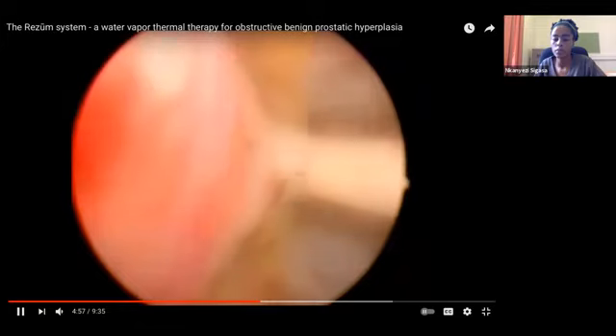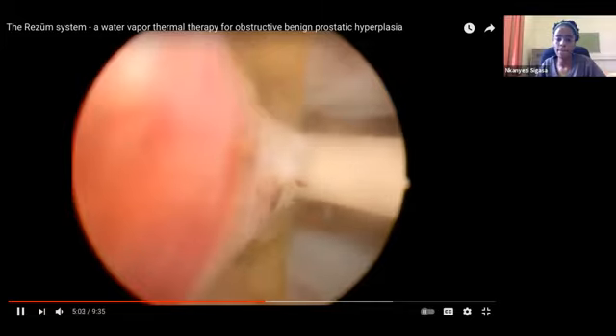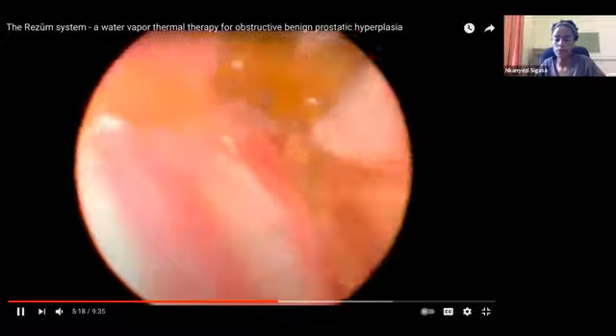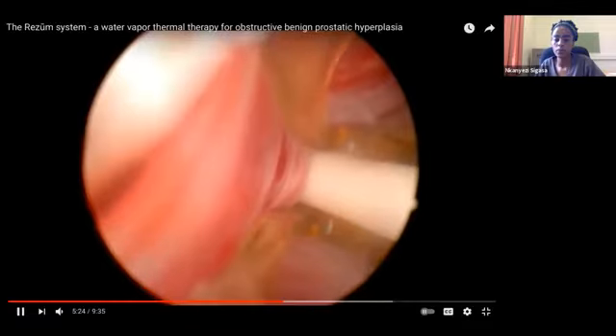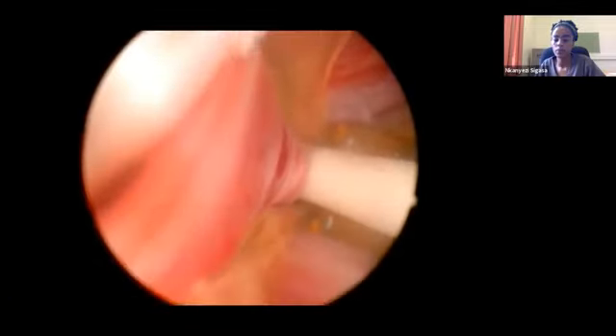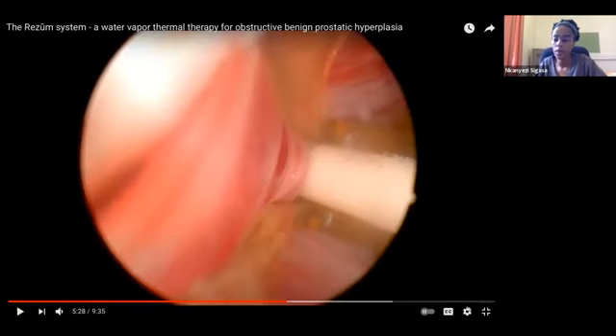After completion of the lateral lobe treatments, the central zone or median lobe tissue may be treated. It is recommended to treat central elevation when there is difficulty entering the bladder or the prostatic urethral angle exceeds 40 degrees. This is done by moving the delivery device to the right or left of the field and entering the tissue at a 45-degree angle, aiming for the middle of the prostatic tissue. The central zone typically only requires 1 treatment. When a median lobe is present, the same procedure is done, but should be completed on either side of the median lobe. And that's basically the Rezum procedure.